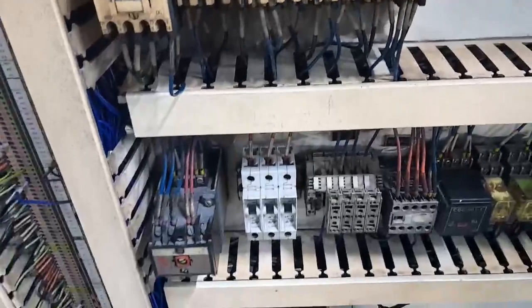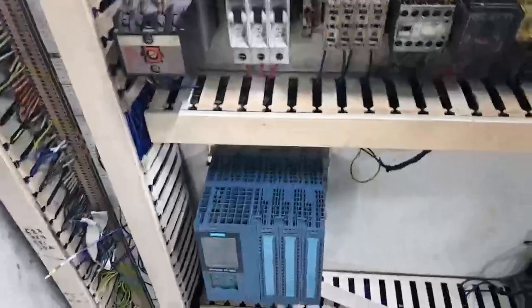Programming errors leading to catastrophic failure. This is another risk. The risk is when incorrect PLC programming or logic errors have occurred. This can cause machinery to malfunction, leading to fatal accidents. The main causes of programming errors leading to catastrophic failures: lack of testing, inadequate documentation, and human error during coding. How do we mitigate these risks? Performing thorough simulation and testing of PLC programs, using version control and following structured commissioning processes with peer reviews would be a way to mitigate.